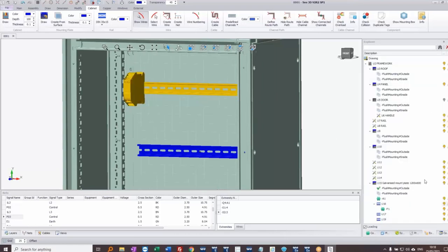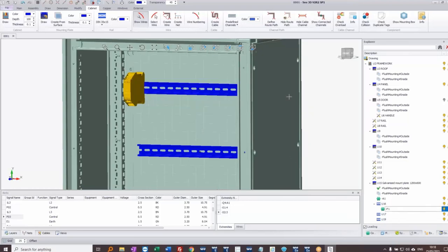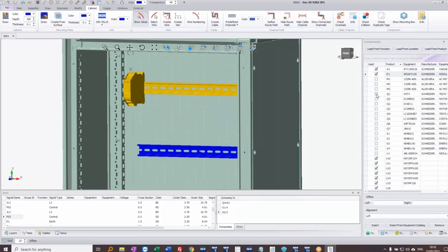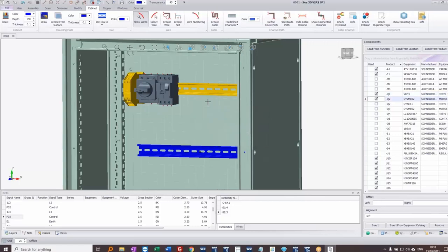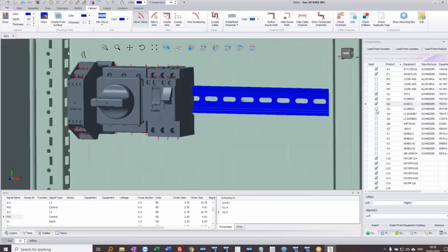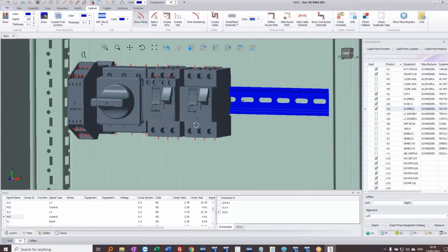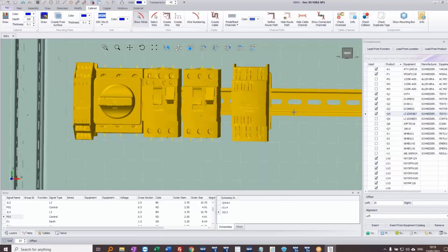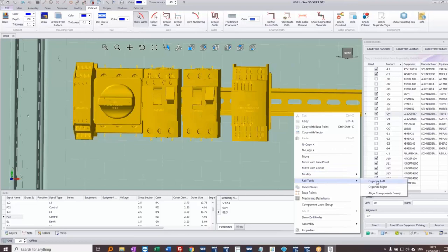I'll select the DIN rail itself and place the next device — a contactor with an auxiliary contact block. I tap K while it's on the drawing and the auxiliary contact snaps into position, demonstrating assemblies of devices that join together. I can leave a gap, or select the rail and specify a 20mm gap for the next placement. I could also select the DIN rail and use rail tools to organize all devices left, with various spacing options.